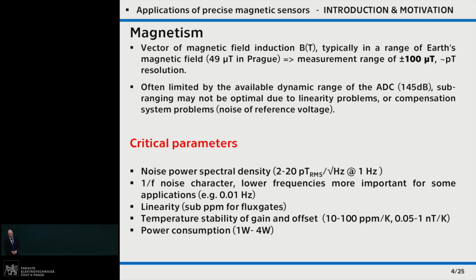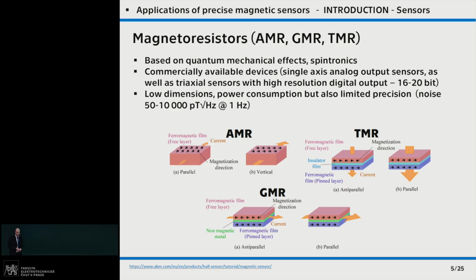As I said, our magnetometers work typically in the range of hundreds of microtesla, and we want to get the best resolution possible, which means several picotesla right now. This means that a fluxgate magnetometer can reach something like 160 dB of dynamic range, which is quite problematic for the electronics because current analog to digital converters can offer something like 145.